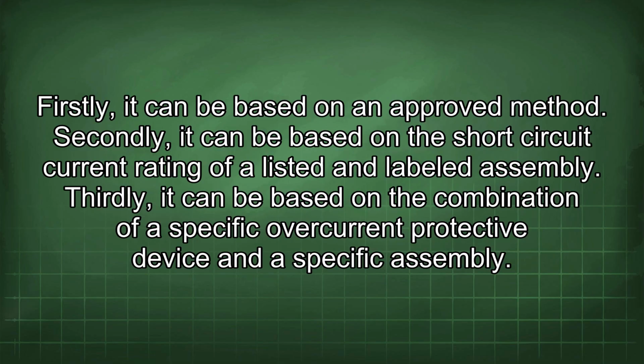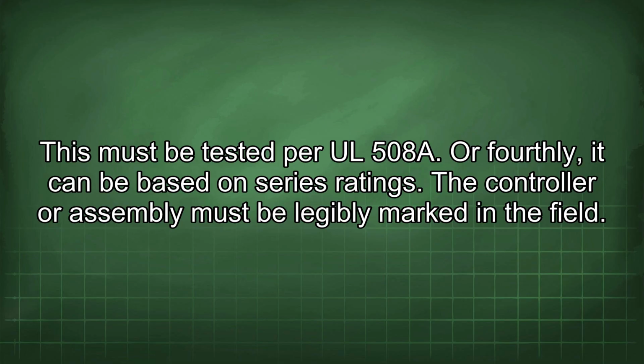Firstly, it can be based on an approved method. Secondly, it can be based on the short-circuit current rating of a listed and labeled assembly. Thirdly, it can be based on the combination of a specific overcurrent protective device and the specific assembly. This must be tested per UL 508A. Or fourthly, it can be based on series ratings.